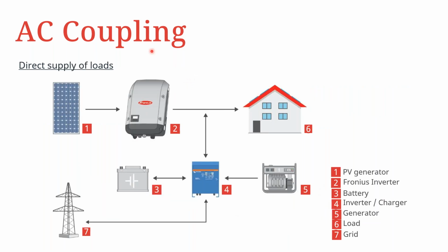When we talk about an AC coupled solution, we are talking about the connection of PV power directly to the loads through the PV inverter, and then any excess energy that is not being consumed directly is supplied to the batteries. In this case, the inverter charger is able to operate in a sort of reverse direction because the Fronius inverter will be connected to the AC output, so it can work in reverse for charging the batteries. You could also have a backup generator, as we can see here, number 5, or a grid which you would like to support with backup power, or if the grid is not very stable, then you form your own microgrid solution for this kind of setup or premises.